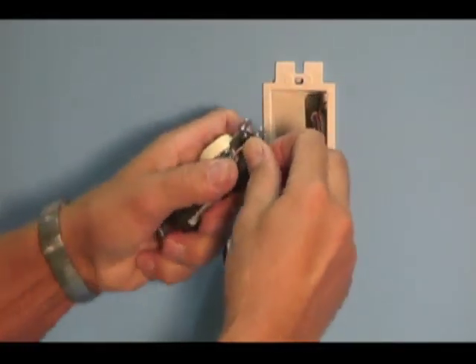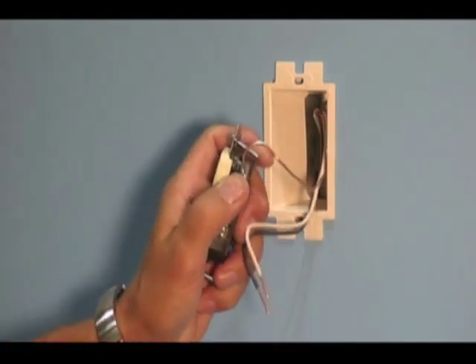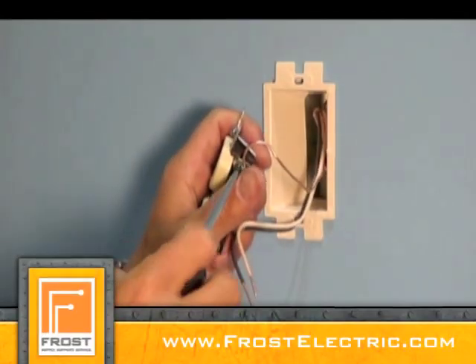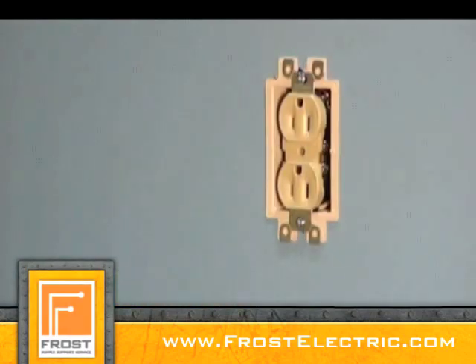That is, a box that's set back no more than a quarter inch in a non-combustible wall and one with no setback in a combustible wall.